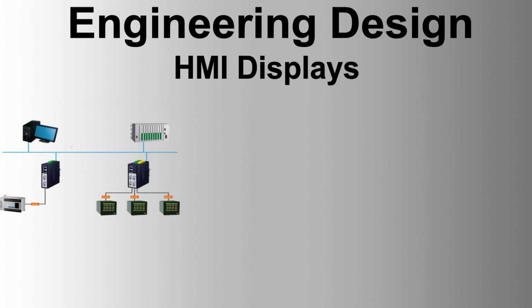Density of information on screens. Graphic displays should not be cluttered, as excessive information may lead to extended search times by the operator and loss of clear direction. There should be no more than 40 live data points per display. Generic graphic template. Specific areas of the screens should be reserved for certain kinds of information, such as graphic titles, navigation targets, and command zones. These areas should be consistent across all displays and should be developed in a generic graphic template.